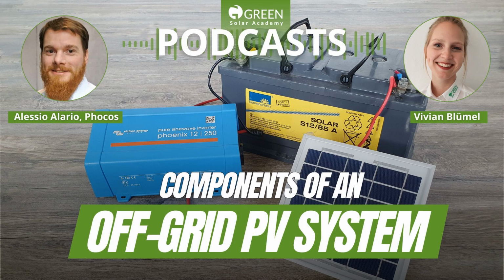With a DC coupled system, it can get a little bit more complicated because, of course, you have a separate charge controller and a separate inverter. So you need to make sure that they work together well. You need to make sure that your low voltage disconnect, for example, is about the same on both of them, or just take that into account. So the complexity is a little bit higher. For AC coupled systems, the complexity gets a lot higher.